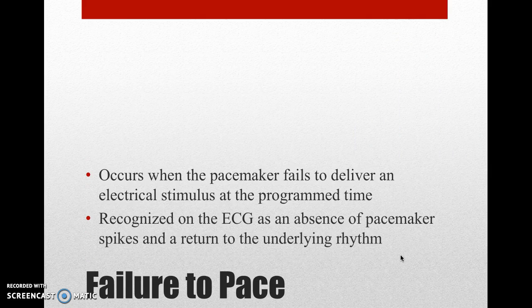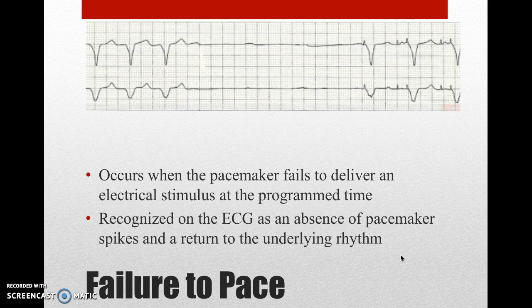Failure to pace is a malfunction that occurs when the pacemaker fails to deliver an electrical stimulus at the programmed time. This is recognized on the ECG as an absence of pacemaker spikes or complexes and a return to the underlying rhythm. Note the loss of any pacing or capturing in the middle of the strip above.